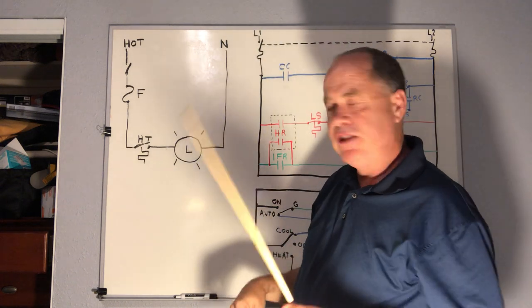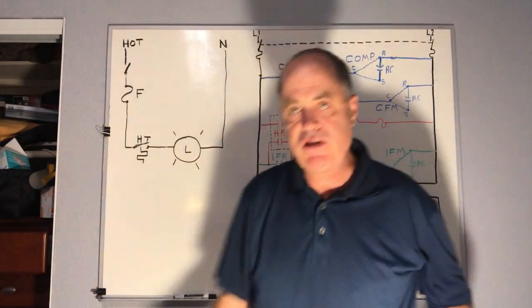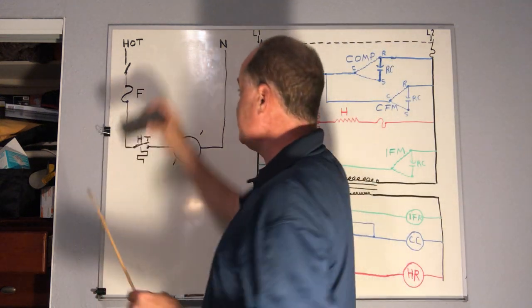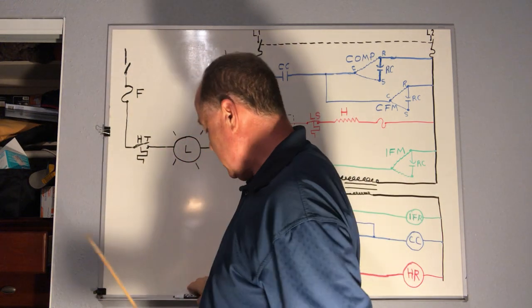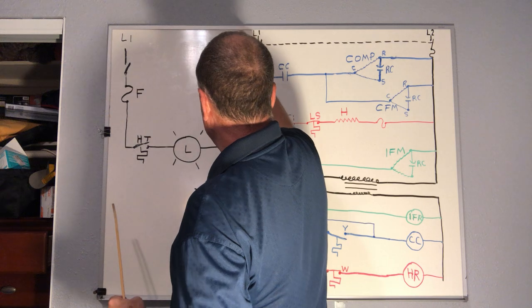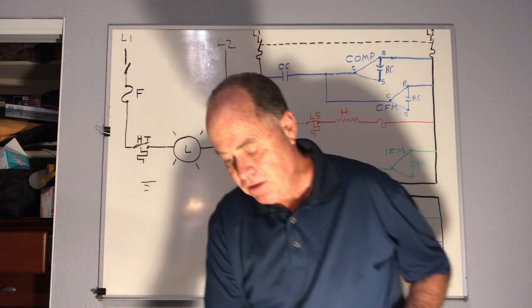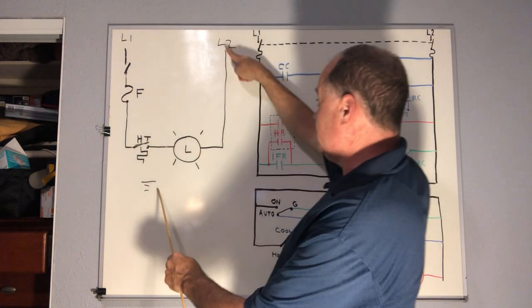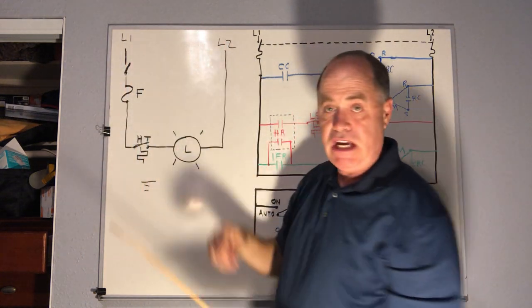Let's try something a little bit different so we can understand the difference between 115 volts and 230 volts. Let's say this is L1 and L2, and then you have a ground. L1 to ground would be 115 volts, L2 to ground is 115 volts, and together it's 230 volts.